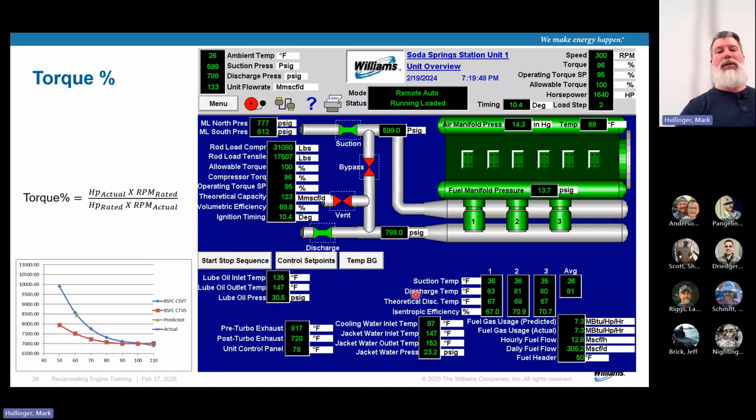If anyone is listening to this later on, that's not a very good thermodynamic explanation, but that's the way I understand it, okay? So can you see that a 2-degree temperature difference is a 3% loss in efficiency? This is thermal efficiency, okay? So we just did that calculation for you on there. It's just kind of a nice little cheat, okay?